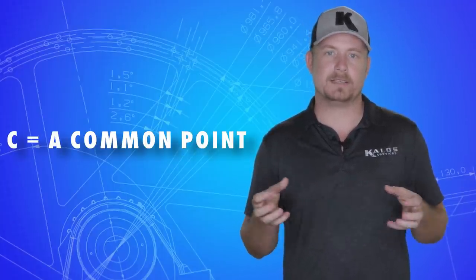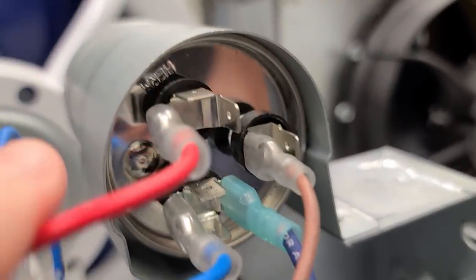In both cases, the C denotes a common point. In the dual capacitor, it's the common point between the fan capacitor and the compressor capacitor, which is marked as Herm.